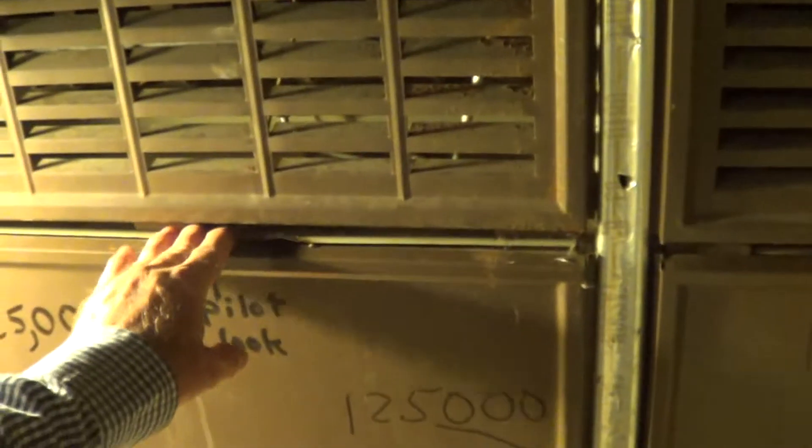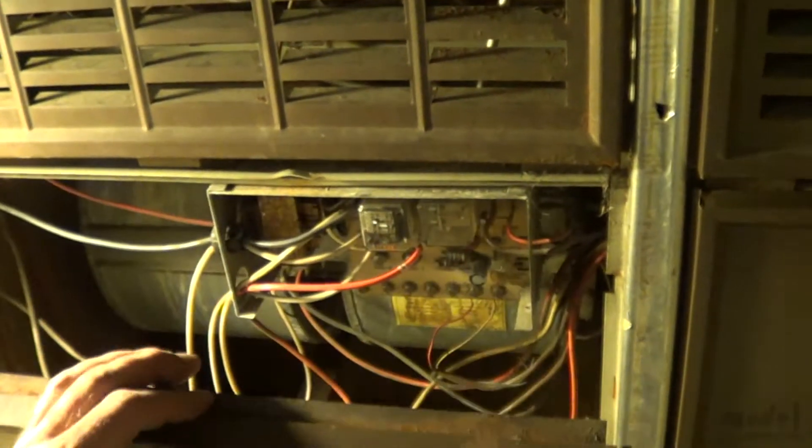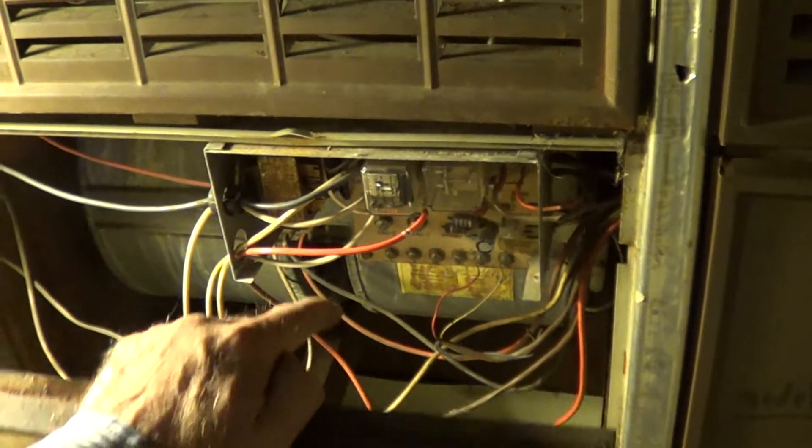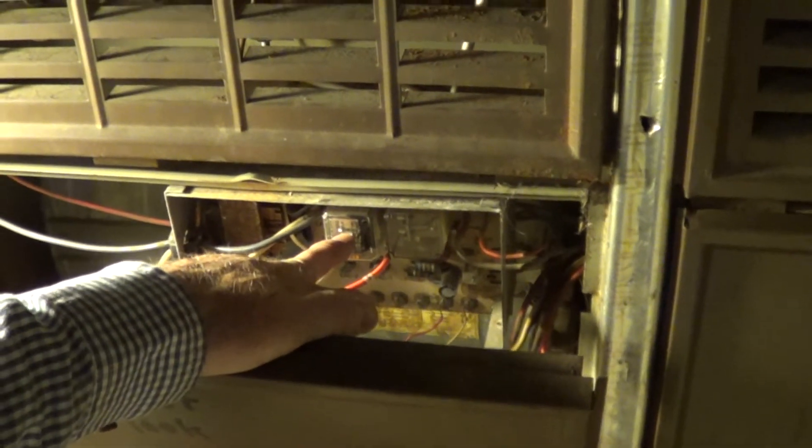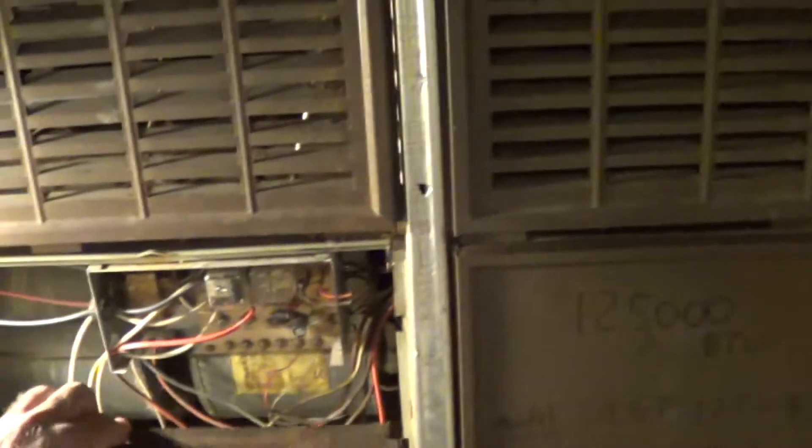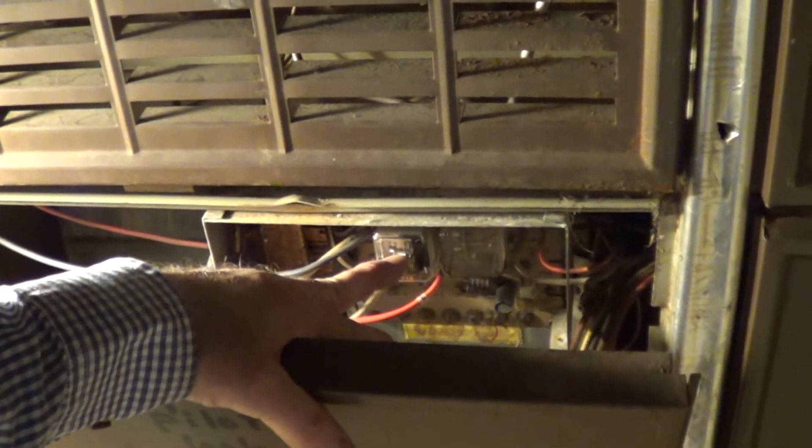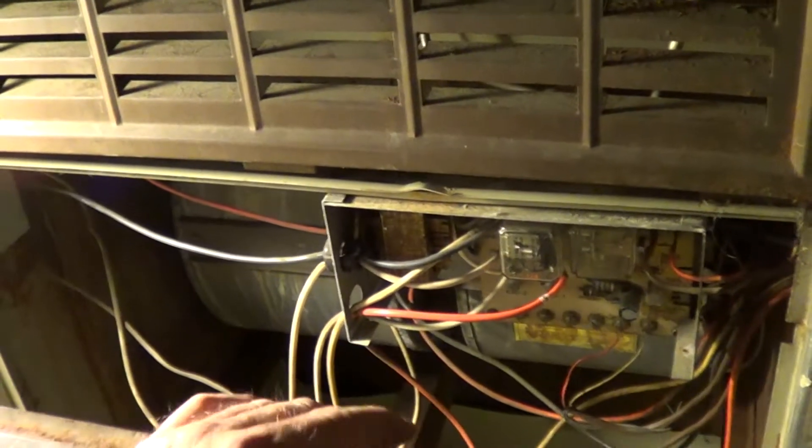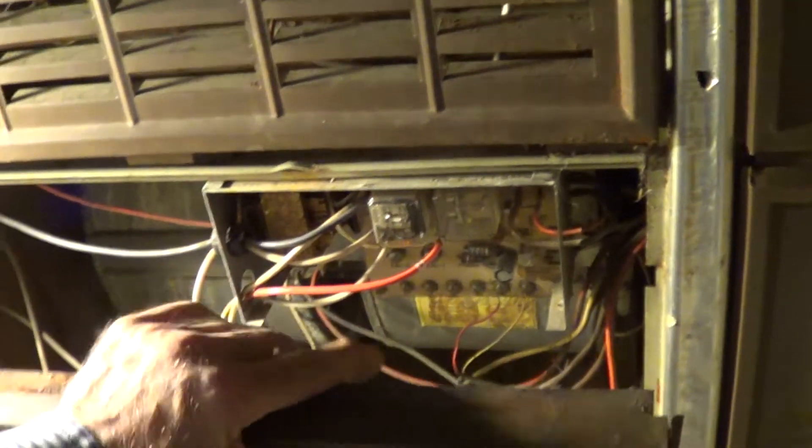Now we're completely off. I'll go over here real quick. Got the unit buttoned up. Now on the left furnace here on this dual one, what can happen sometimes is this relay will stick if it gets older and the fan will run all the time. That's on a twinned unit. If you pull this off and bump this really hard, you'll unstick the relay and it'll work. So I've got to really replace this board here.